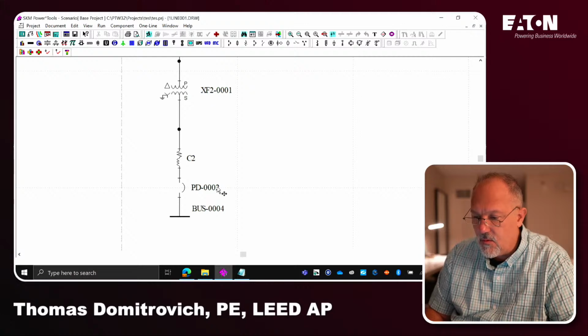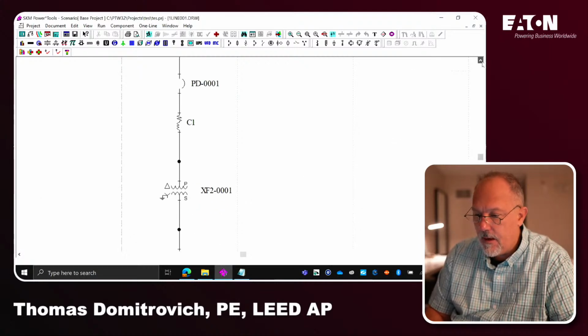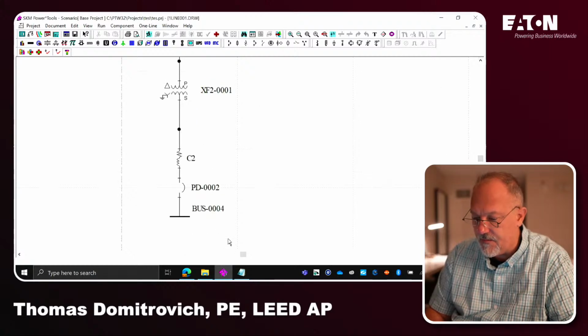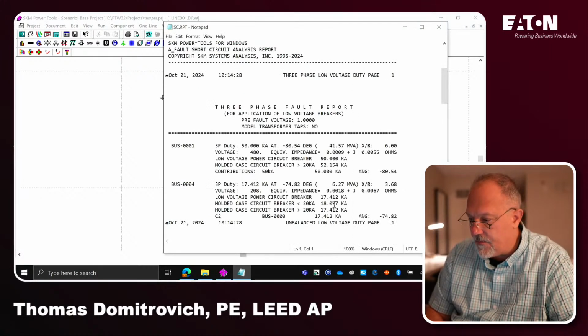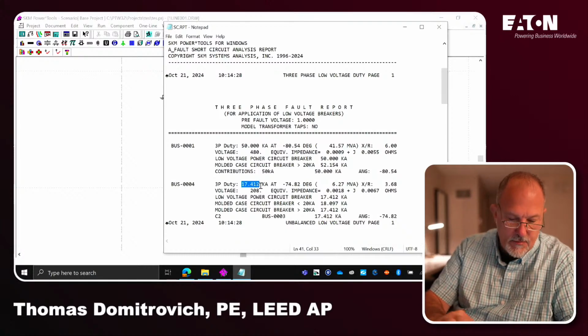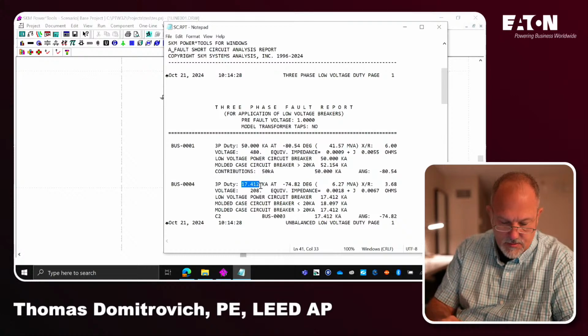I have bus 4 for the available fault current. And that's the only bus, so I'm looking for bus 4. Bus 4 fault current is right here, 17,412. And I am going to use the 500 kVA base values, 208. I'm looking for my fault current, I per unit.